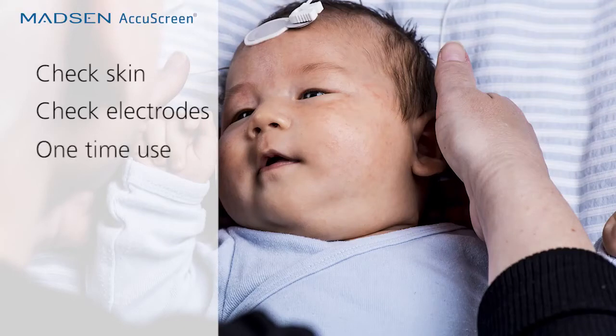Also, check if the electrodes are dried out or very old. Electrodes have a limited lifetime, even if they are stored properly. Check if all electrodes adhere well to the baby's skin. If not, you may have to remove the electrodes, re-prep the baby's skin, and use new electrodes. Do not use the previous electrodes, since these probably have limited adhesion since they have been attached to the baby's skin once. Finally, check and make sure the electrode cable clips are firmly attached to the electrode and that the metal on the electrode clips is not corroded and is free of debris.